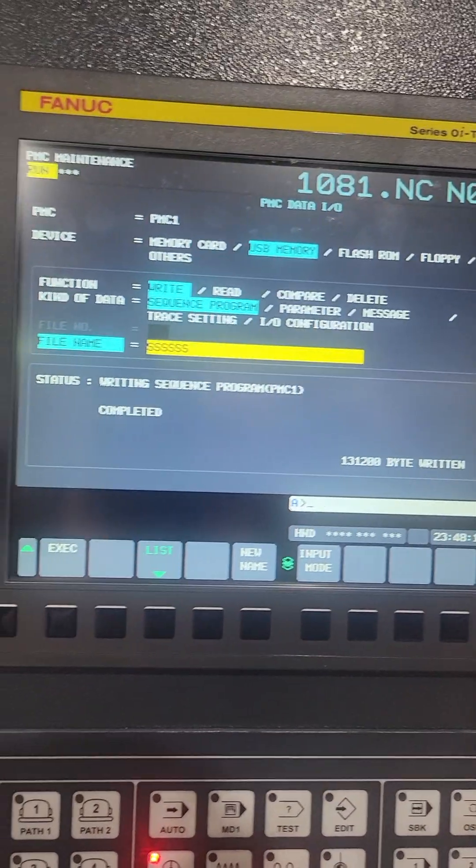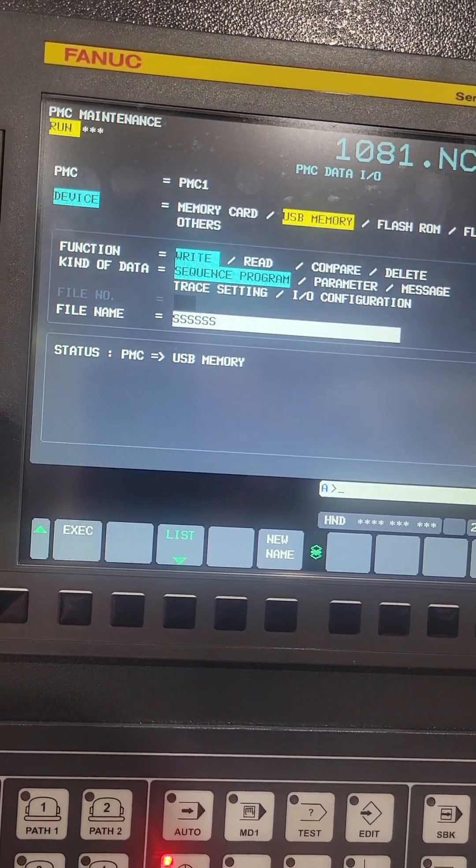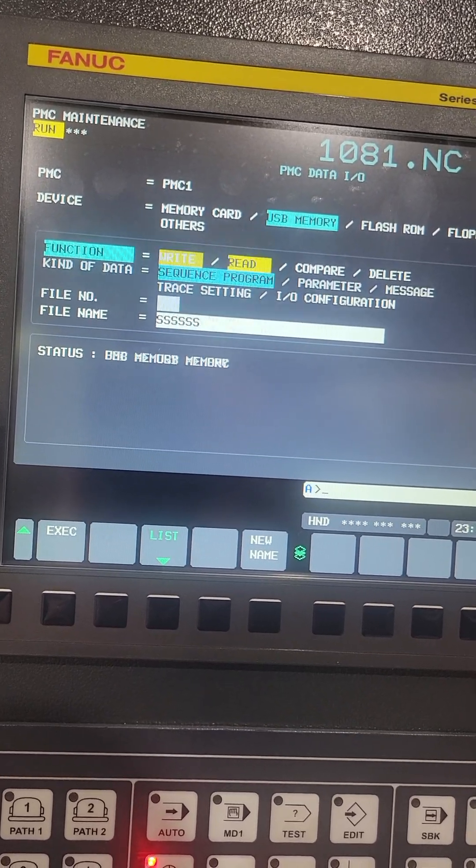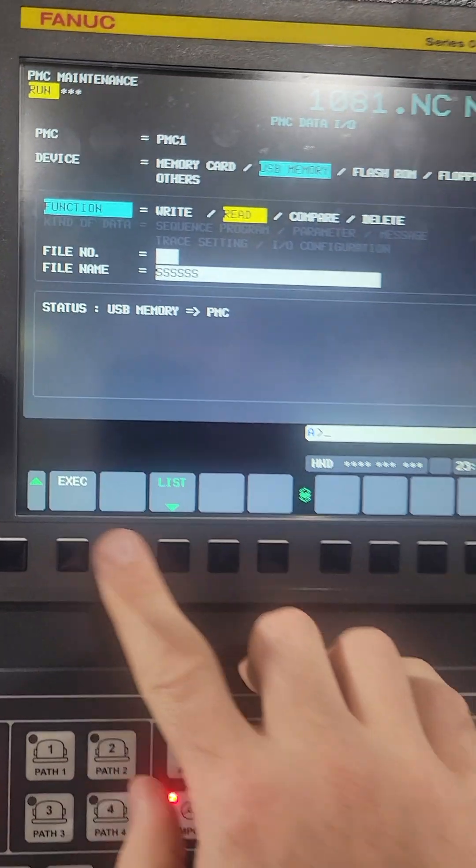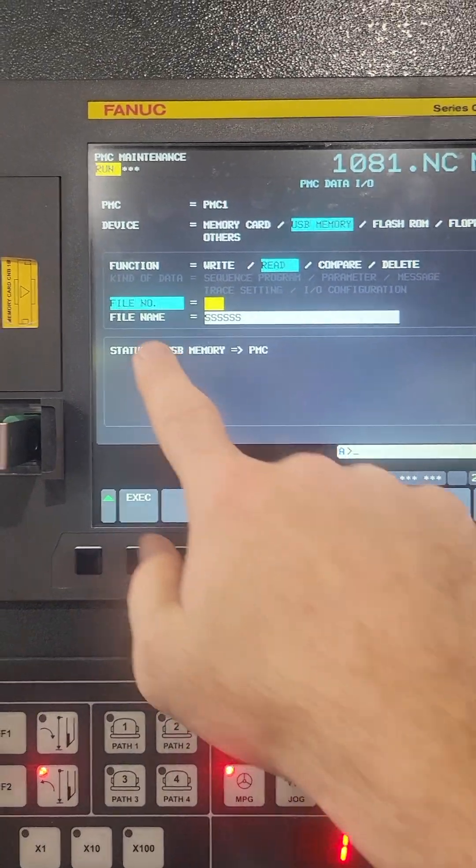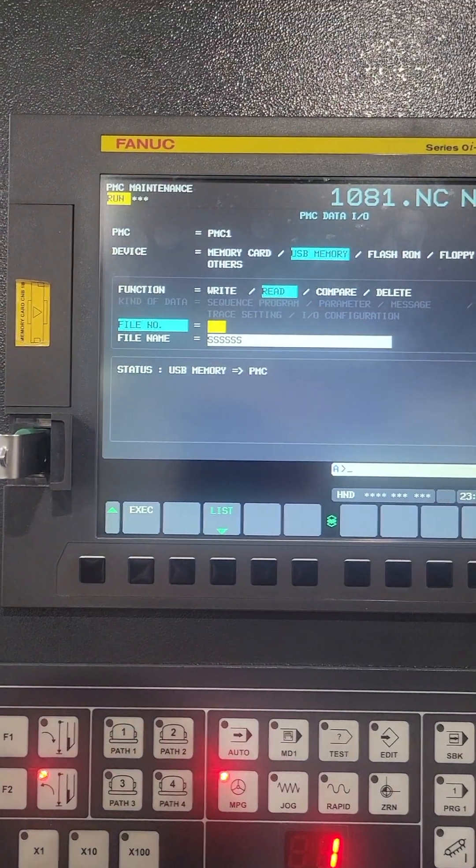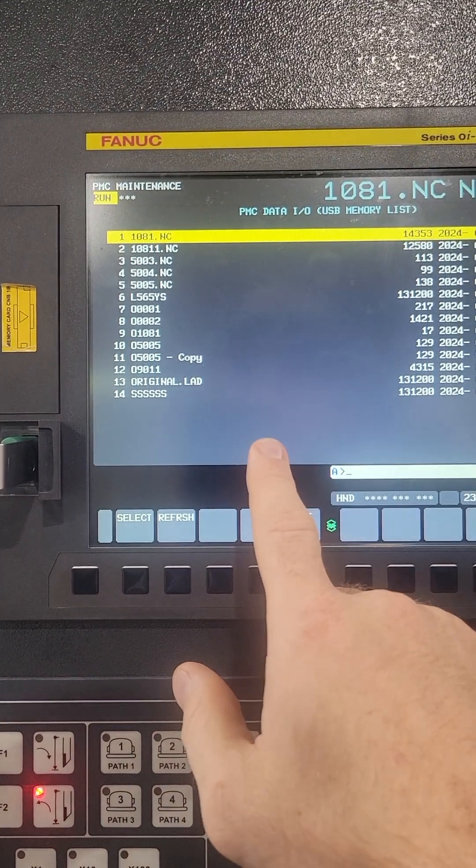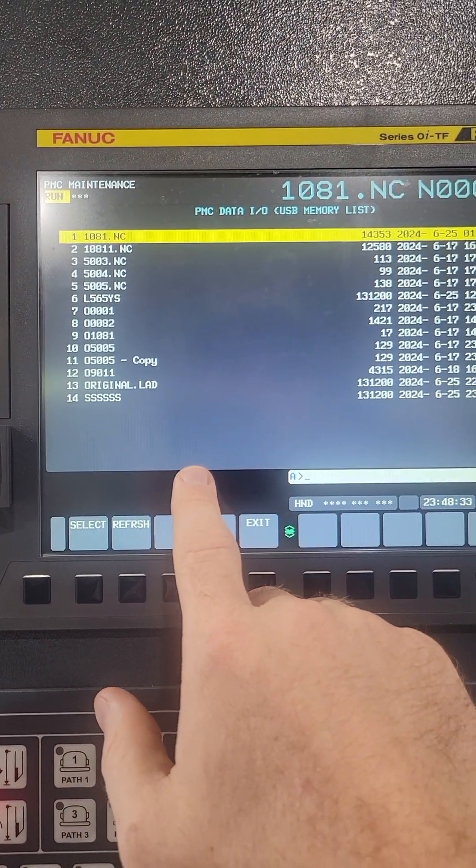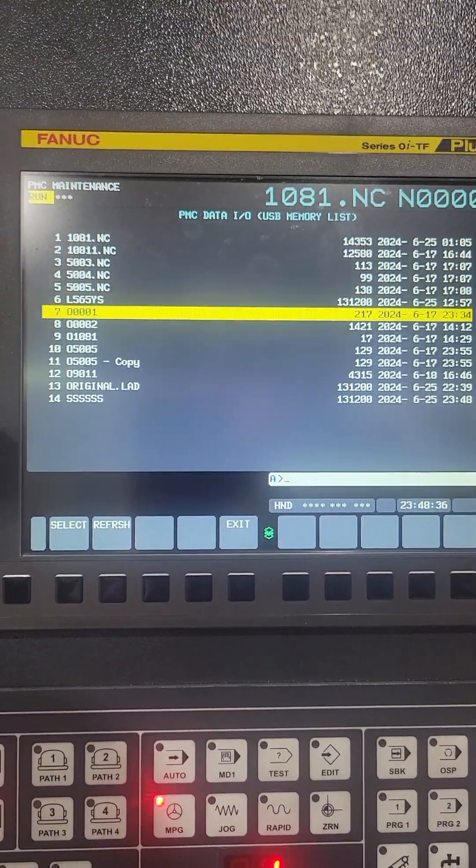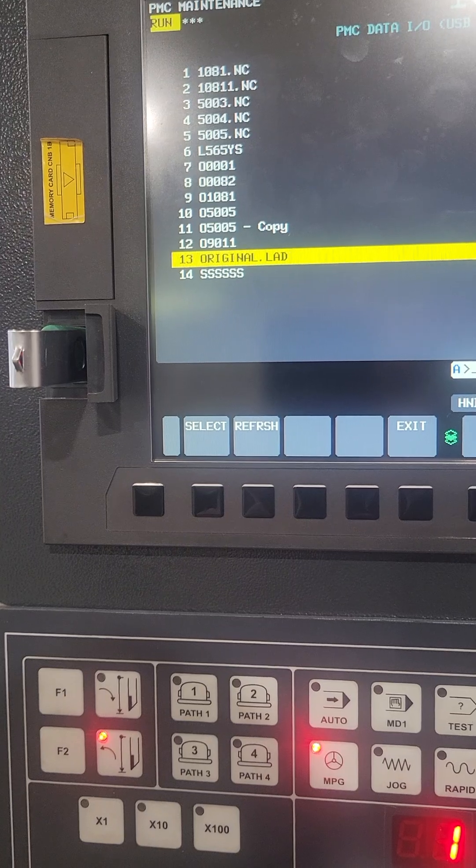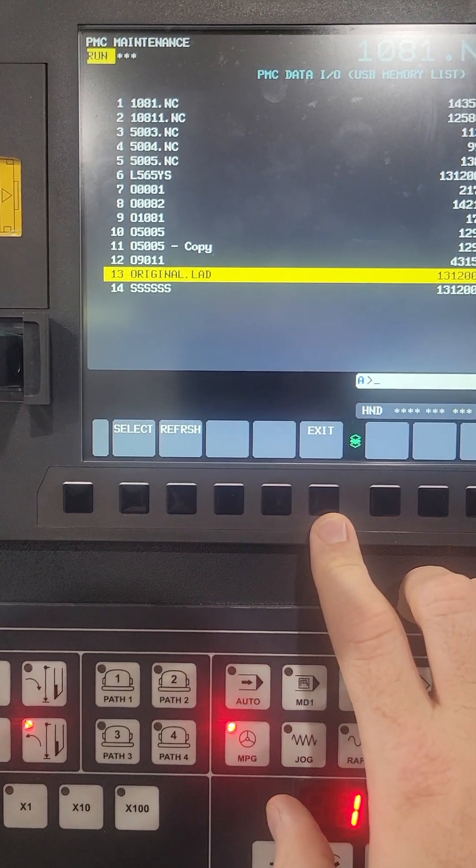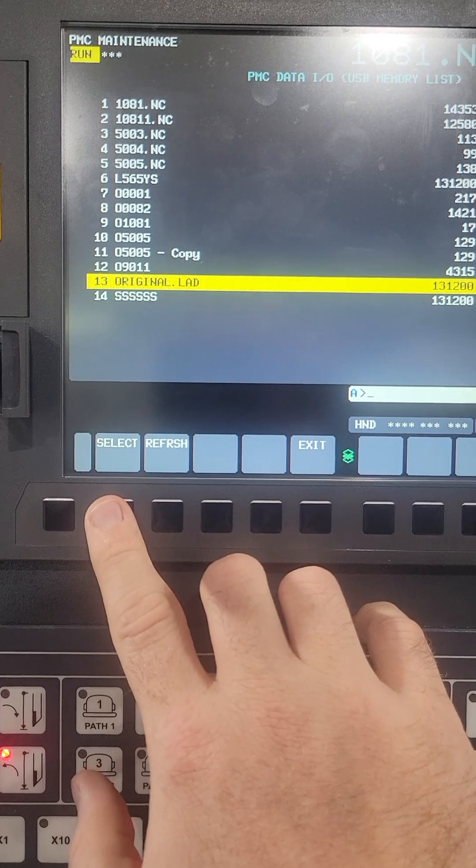Okay, then I'm going to come up here and set this to read from my USB to my PMC. So I'm going to come down to file name, hit list, and this will jump into whichever directory you're using. So I'm using my USB. If I go into here and go to the original.lad, LAD for ladder, hit select.